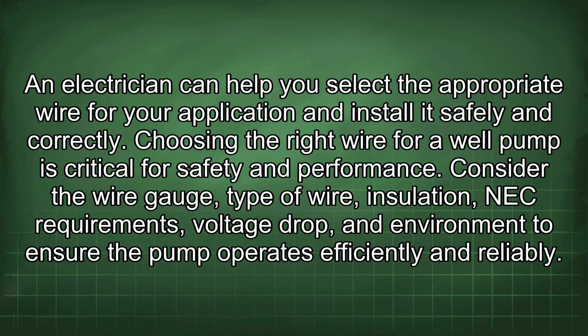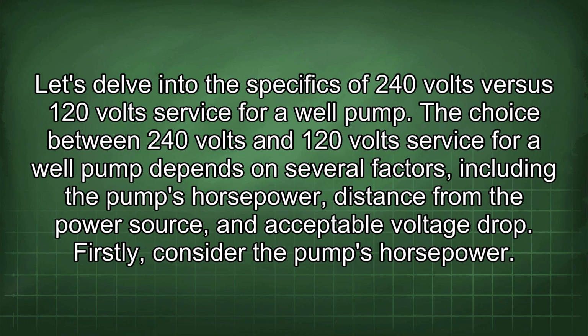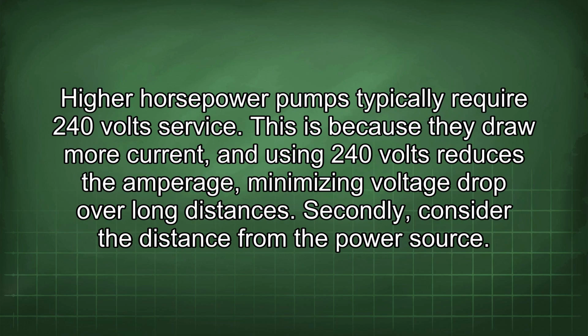Let's delve into the specifics of 240 volts versus 120 volts service for a well pump. The choice between 240 volts and 120 volts service for a well pump depends on several factors, including the pump's horsepower, distance from the power source, and acceptable voltage drop. Firstly, consider the pump's horsepower. Higher horsepower pumps typically require 240 volt service. This is because they draw more current, and using 240 volts reduces the amperage, minimizing voltage drop over long distances.